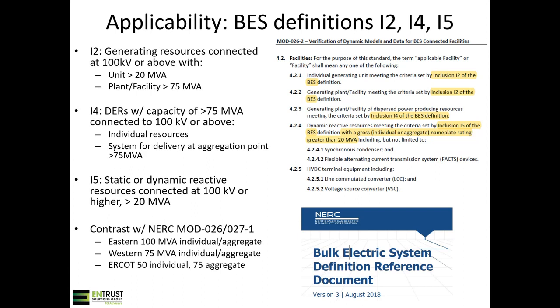We now also have applicability for transmission-level connected static or dynamic reactive resources—so transmission-level StatComs. If you have capacitor banks or reactors controlled through a dedicated controller, rather than just manually toggled, any type of representation needed to capture that would apply.